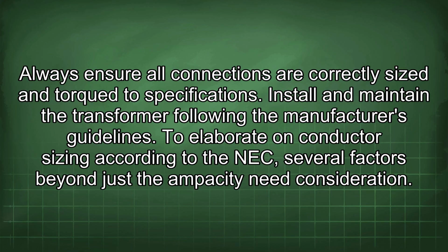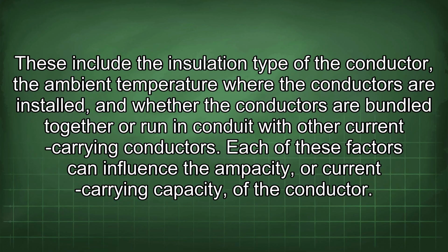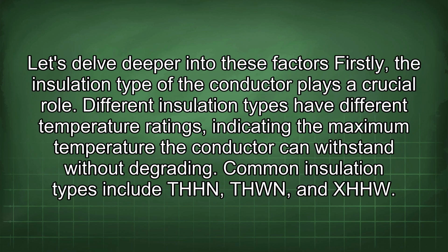To elaborate on conductor sizing according to the NEC, several factors beyond just the ampacity need consideration. These include the insulation type of the conductor, the ambient temperature where the conductors are installed, and whether the conductors are bundled together or run in conduit with other current-carrying conductors. Each of these factors can influence the ampacity or current carrying capacity of the conductor. Let's delve deeper into these factors.